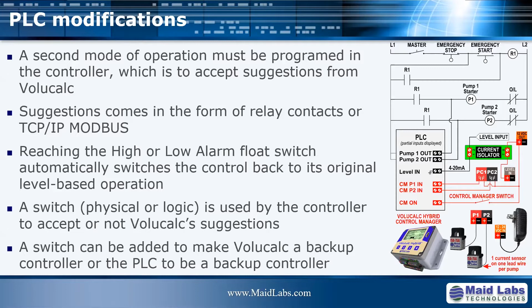Yes, the Volucalc could be a controller, but we never thought it wise for the monitor to be the controller, because if the controller failed, I don't see how the monitor would not fail at the same time and report it. So that's the reason why, even if the instrument has everything it needs to be a controller, we never wanted the instrument to be a controller.